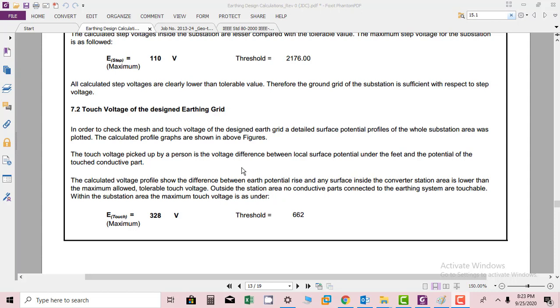In order to check the mesh and touch voltage of the designed earth grid, a detailed surface potential profile of the whole substation area was plotted. The profile graphs are shown in the above figures. The touch voltage picked up by a person is the voltage difference between the local surface potential under the feet and the potential of the touched conductive part.